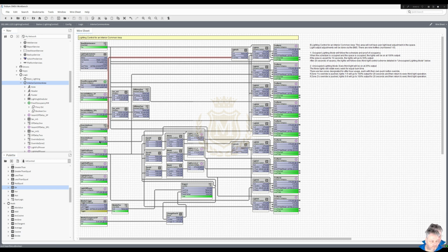And fire zone 2. And the last 4 ones, 6, 7, 8 and 9 are on. And again, 20 seconds it will go off. But we know this. And it's counting up there as well. So these are all 3.4s. And they've gone off as well. Let's reset the maintenance. They've all gone back to zeros. Good, we know that works.